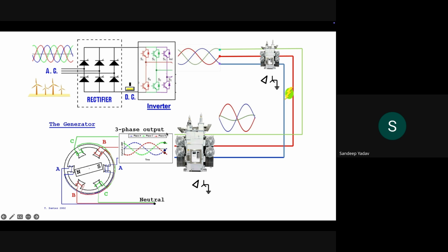So all the synchronous machines, whatever their size is, whatever their machine parameters are, their short circuit response is almost identical. They behave almost the same way, which is easily predictable. However, in case of inverter-based resources, it could be very different depending upon the type of control algorithm, the type of voltage ride through that a particular original equipment manufacturer, or the OEM, which is the manufacturer of the inverter, has built into its voltage source converter. So the short circuit response of one manufacturer may considerably vary from another manufacturer, given the type of control algorithm that has been used.